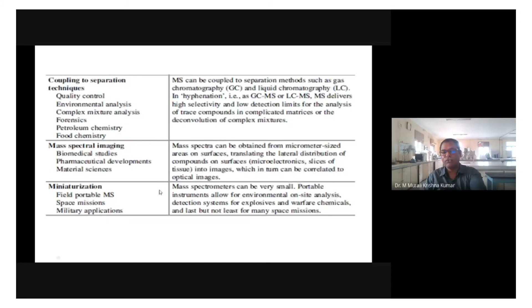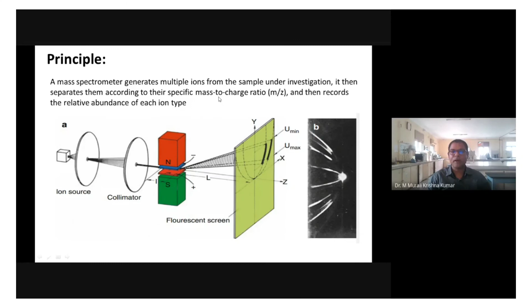So in principle, in case of mass spectrometry, a mass spectrometer generates multiple ions from the sample under investigation. It then separates them according to their specific mass to charge ratio and then records the relative abundance of each ion type. Okay, so this is in brief the principle of a mass spectrometer. So here we have an ion source, and ions are passed through an aperture to generate an ion beam that will be allowed through an analyzer, and then the ions are segregated according to their mass so that they are determined by using a detector. Okay, so this is in simple terms the principle of mass spectrometry. Whatever the signal that we are getting is actually the mass to charge ratio.